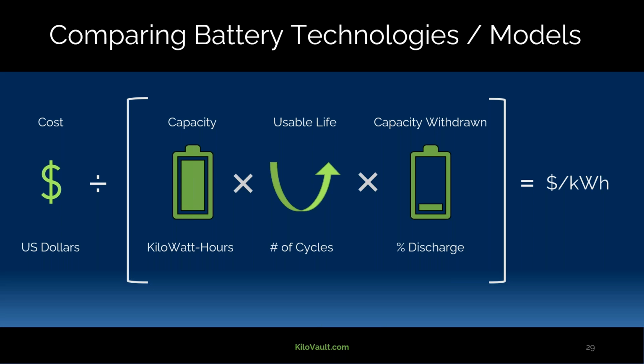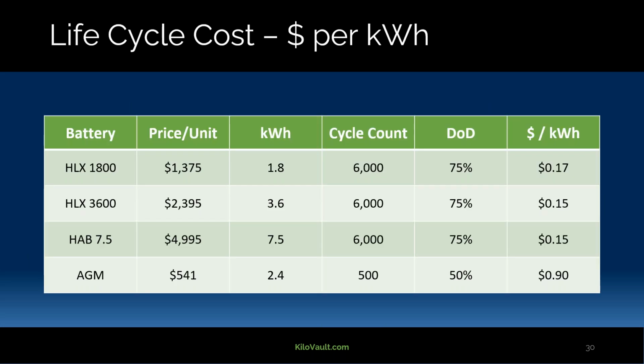Yeah, that sounds great. So just to piggyback on what Jake was saying here, when we are trying to evaluate the cost effectiveness of lithium batteries specifically, it's really important to break it down based on their total life cycle cost. So a tangible or quantitative way to do this is to take that total cost and then divide it by not only the kilowatt hours, but also factoring in the total number of cycles you're going to get out of the battery and the percentage of available capacity or usable capacity. And what you'll see, Jake, if you switch to the next slide, is that the cost per kilowatt hour per life cycle, or over the lifespan of the batteries, is tremendously lower for lithium iron phosphate batteries such as the KiloVault HLX and HAB series batteries as compared to your typical AGM battery.